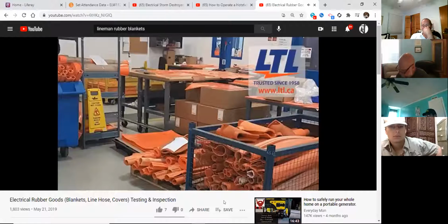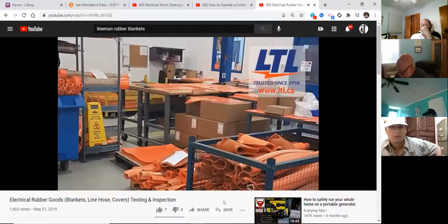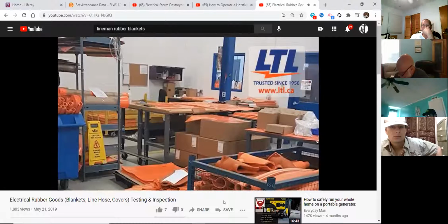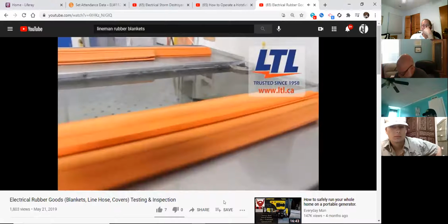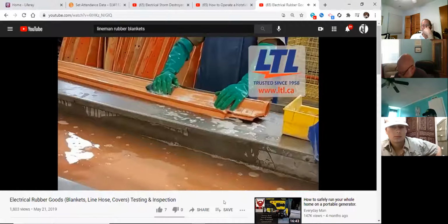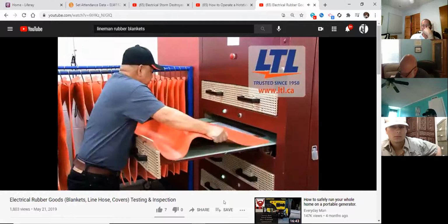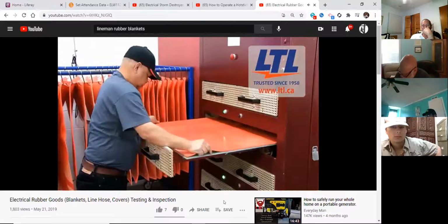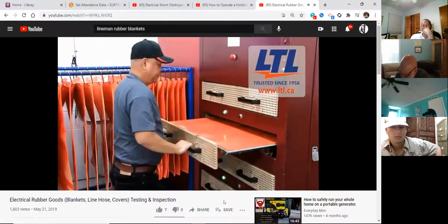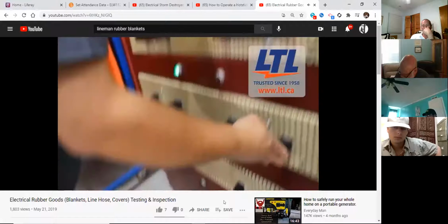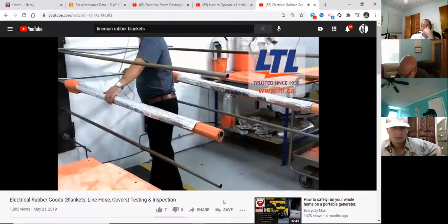When your PPE arrives at LTL, the equipment is checked in and recorded. It is then washed with a mild detergent and water and air dried. Electrical test is performed on blankets per ASTM F479 and the line hose and covers per ASTM F478.